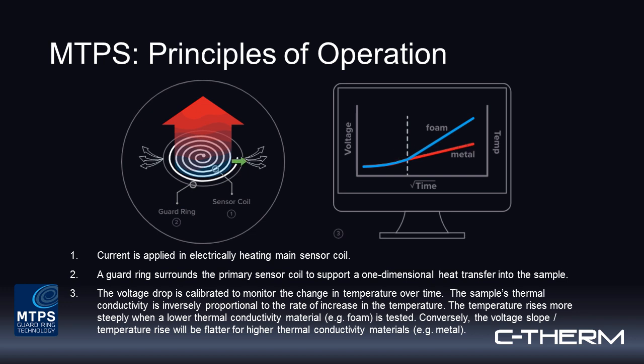A little bit of nuance and context here. So the measurement times are kept by design to be intentionally short. So a typical test time is in the range of 1 second. This is a very quick measurement. If you exaggerated those test times, certainly you would start to lose heat laterally in the sample, but because this is a very short duration pulse, that guard ring is proven to be very effective within that time scale.